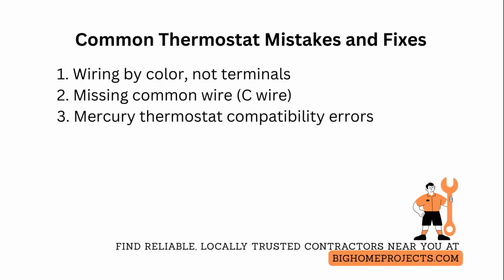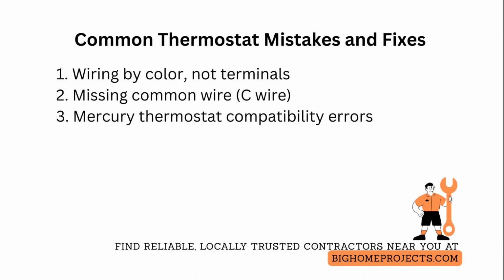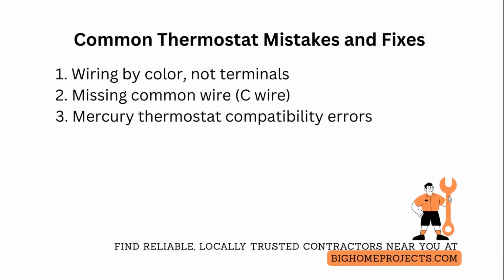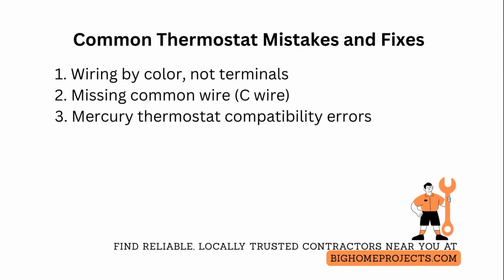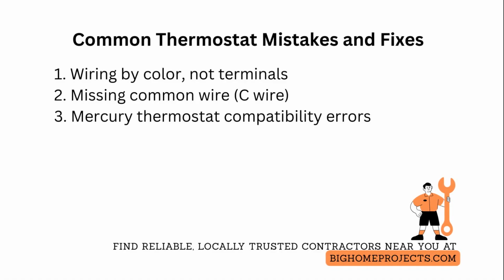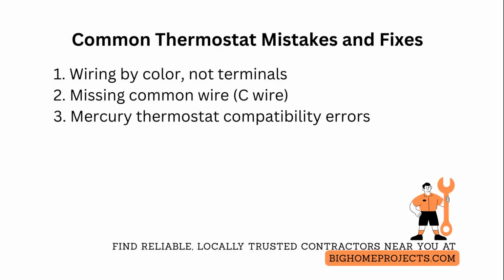One of the frequent problems is compatibility errors with old mercury thermostats and non-standard systems that use proprietary controls. Fix by tracing which 2 wires close the circuit for heat and cool, consulting the equipment manufacturer for wiring diagrams, and if needed, use an isolation relay or interface module to translate the old control signals to modern digital thermostats.